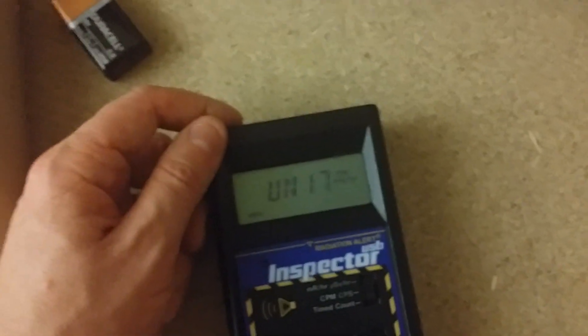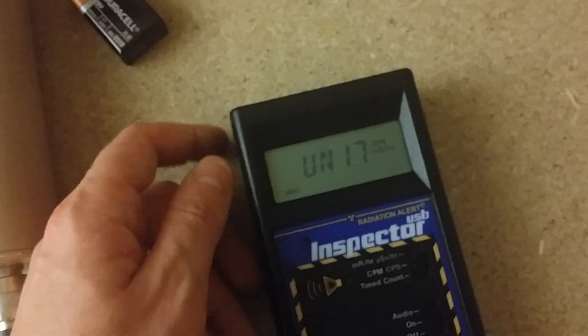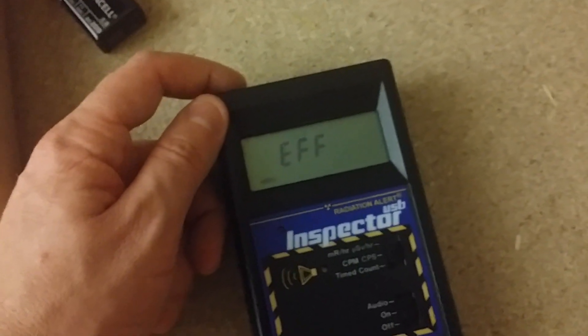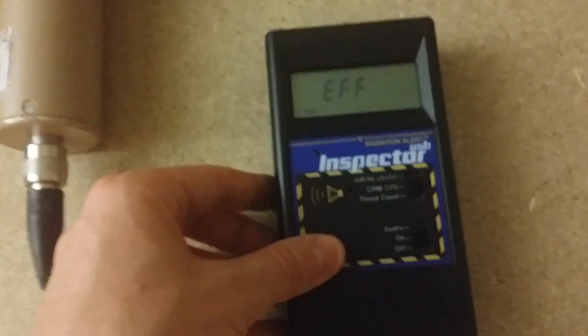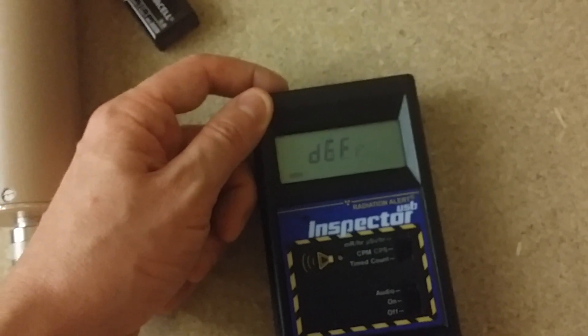In the menu: data logging turns it on and off; units lets you switch between counts per minute, milliroentgens per hour, microsieverts per hour, and counts per second — use counts per second or counts per minute, not actual energy units. Efficiencies let you set this for various radionuclides like Cs-137 or Co-60, with pre-programmed efficiencies so the device can do correct dose readings in microsieverts per hour.